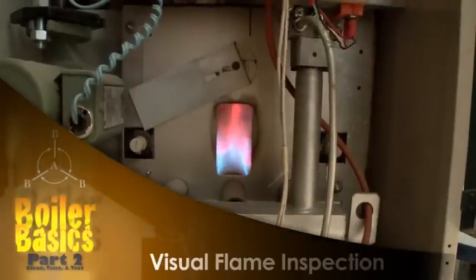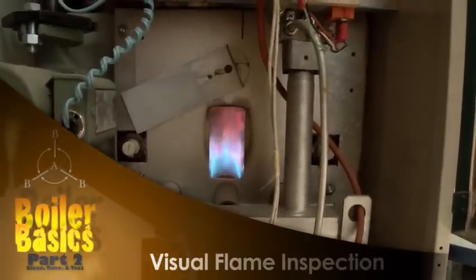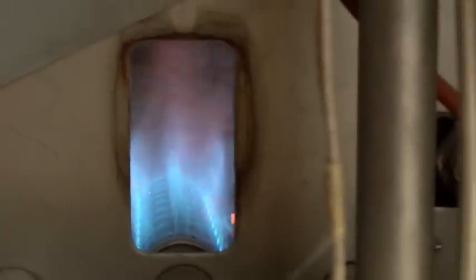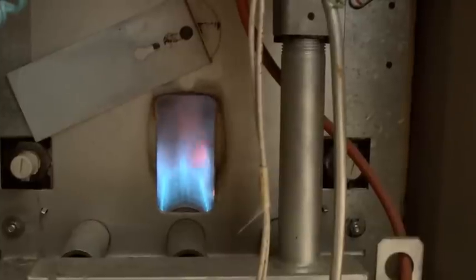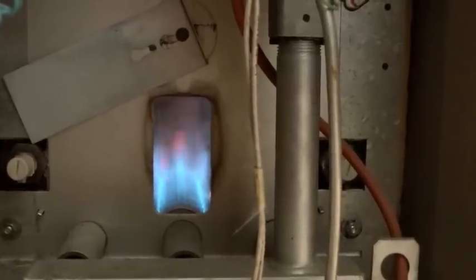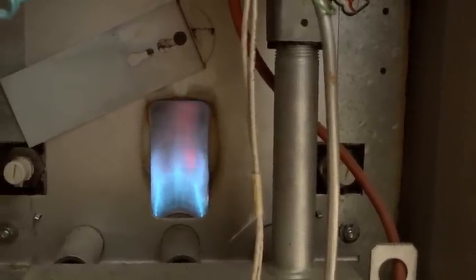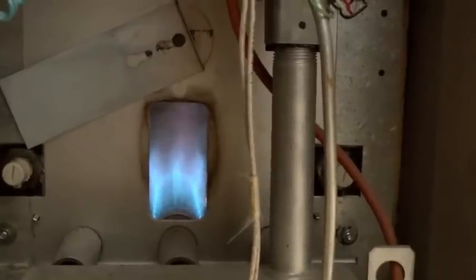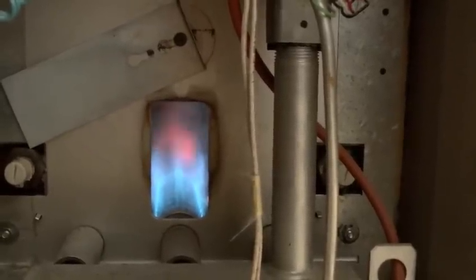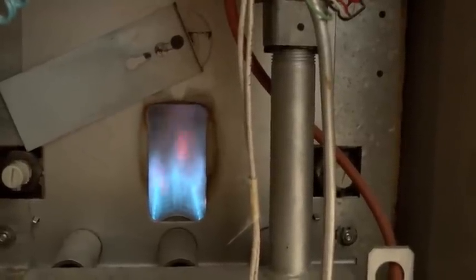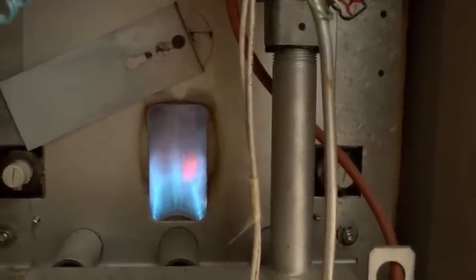So we're looking at the flame here on this boiler, and we do have a really nice blue tipped flame, nice cone shaped, which is what we want. And we do have a little bit of these little red tipping on the end, and that's not uncommon. The main thing we're looking at is the main mantle of the cone and the inner mantle of the cone, and those are nice and crisp.